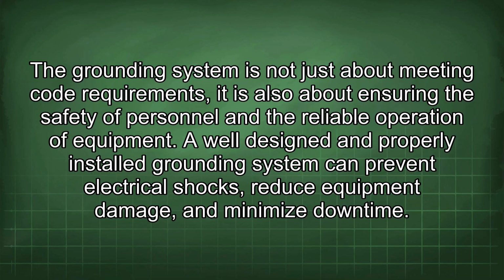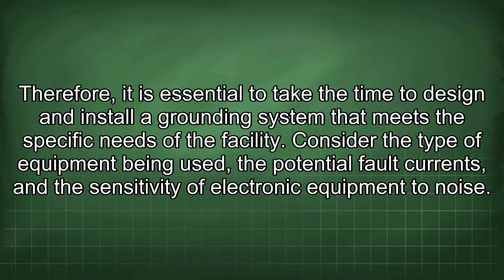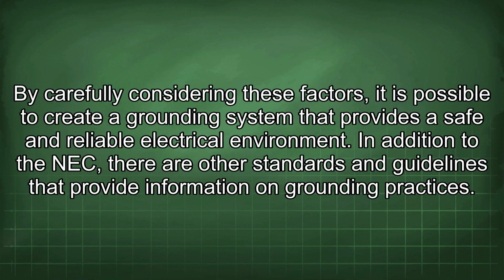The grounding system is not just about meeting code requirements, it is also about ensuring the safety of personnel and the reliable operation of equipment. A well-designed and properly installed grounding system can prevent electrical shocks, reduce equipment damage, and minimize downtime. Therefore, it is essential to take the time to design and install a grounding system that meets the specific needs of the facility. Consider the type of equipment being used, the potential fault currents, and the sensitivity of electronic equipment to noise. By carefully considering these factors, it is possible to create a grounding system that provides a safe and reliable electrical environment.